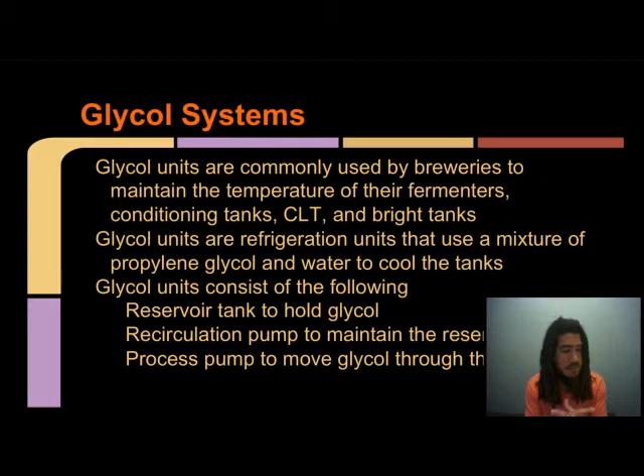Glycol systems. So, glycol units are commonly used by breweries to maintain the temperature of all their fermenters, conditioning tanks, cold liquor tanks, and bright tanks. So glycol units are essentially refrigeration units. They use a mixture of food-grade propylene glycol and water that run around the tanks through their jackets or the cooling coils in foeder's case in order to cool the liquid in the tanks.